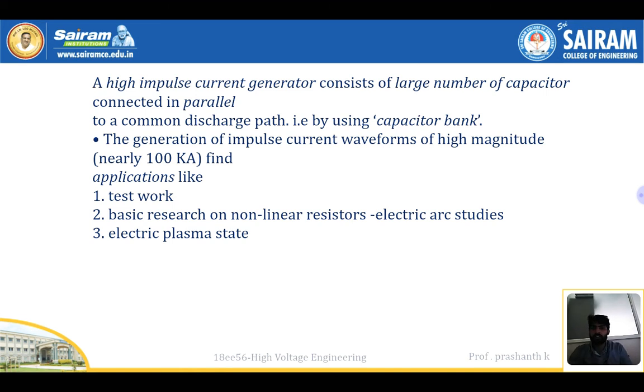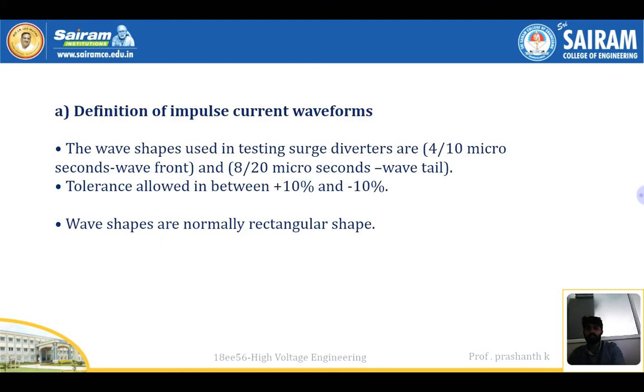A high impulse current generator consists of a large number of capacitors connected in parallel to a common switching path, that is, a capacitor bank. If you visit any power system or substation, there will be a capacitor bank present. The generated impulse current waveform has high magnitude, nearly 100 kiloampere. It finds applications like test work, basic research on nonlinear resistors, electric arc studies, and electric plasma state. Everything is available.